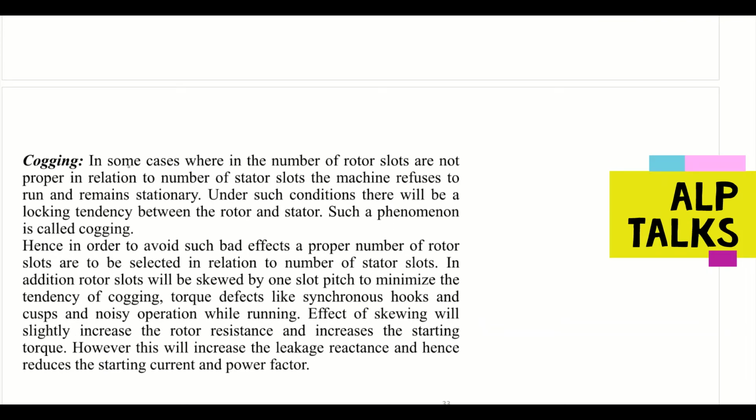So, what about cogging? In some cases where the number of rotor slots is not in proper relation to the number of stator slots, the machine refuses to run and remains stationary. Under such conditions, there will be a locking tendency between rotor and stator. Such a phenomenon we call cogging.